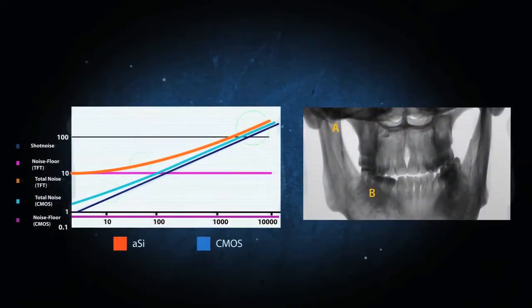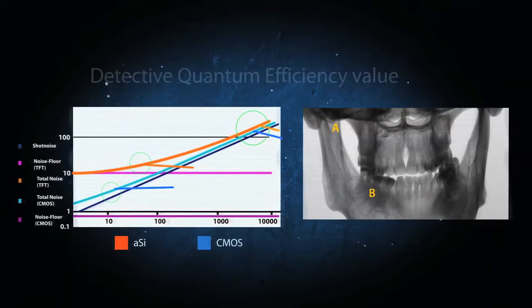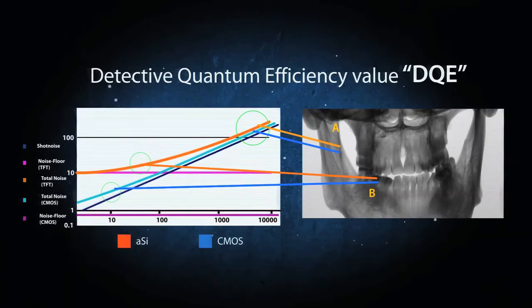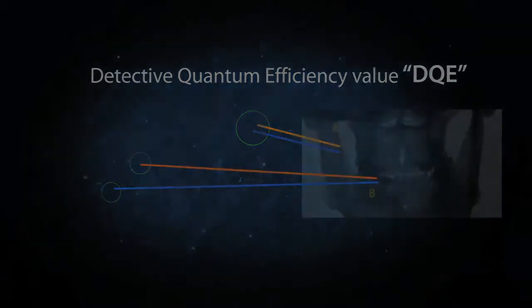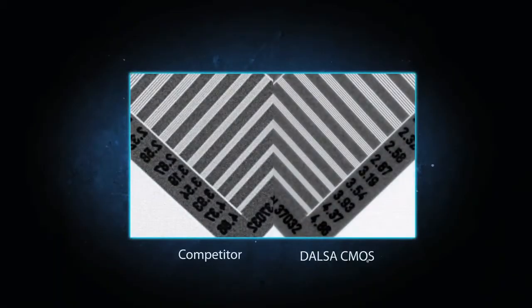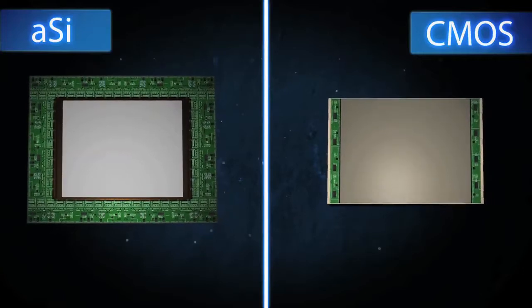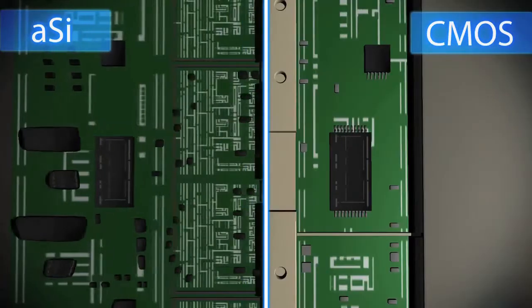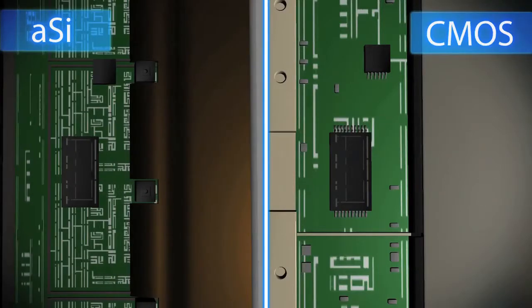X-ray detector performance is measured by a detective quantum efficiency value or DQE. At low dose, you can see the difference both in the DQE graph and in the images. Another advantage of our CMOS detectors over amorphous silicon is our ability to combine the detector and processing electronics on the silicon.